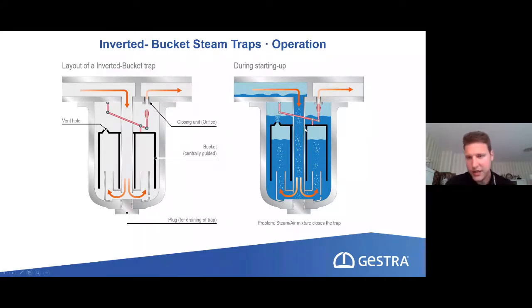And the second problem might be what's with air. If air comes to the steam trap, the bucket will be lifted up and also be closed. That's the reason why we have to do something, because the air would not disappear from the bucket. It will stay here and will always swim above the water line, which will keep the steam trap blocked. To make this work, we have to do a little drilling here, and this little drilling will allow the air to leave if necessary. But this then is also a very small part where we can have steam losses.